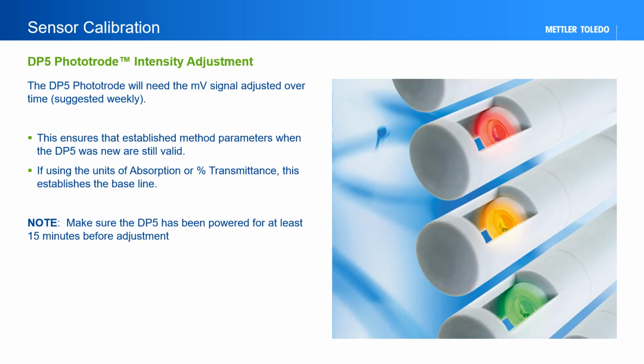The DP5 Phototrode will need the millivolt signal adjusted over time. Weekly is suggested. This ensures that established method parameters from when the DP5 was new are still valid. If using the units of absorbance or percent transmittance, this establishes the baseline. Please note and make sure that the DP5 has been powered for at least 15 minutes before adjustment.